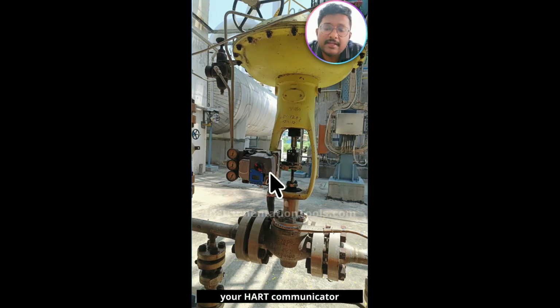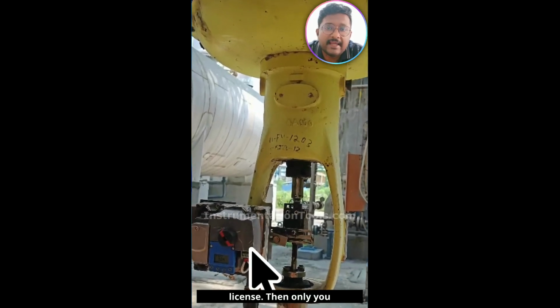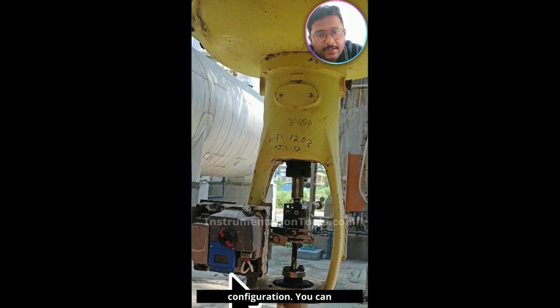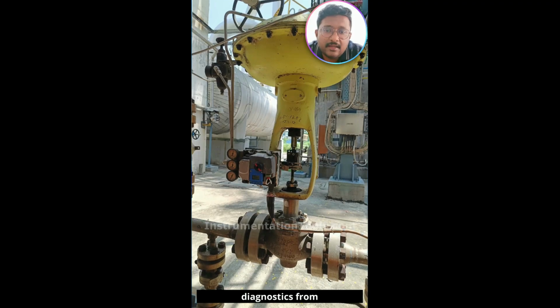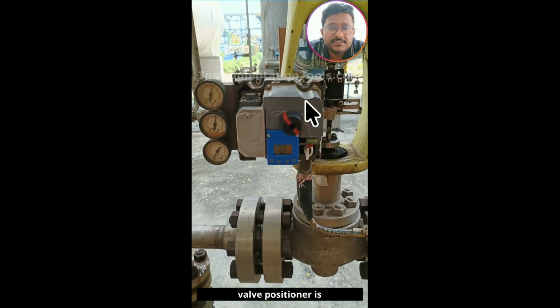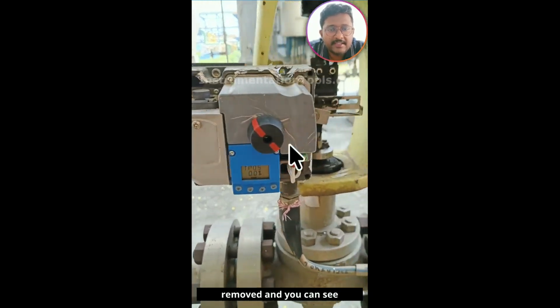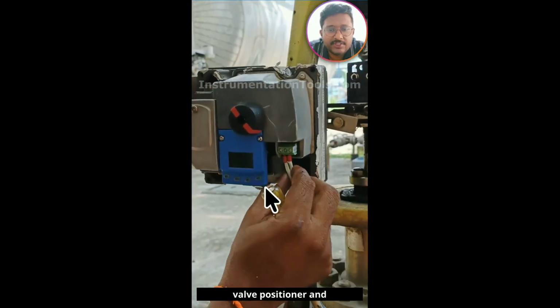Remember, your HART communicator must have a fieldbus license. Then only you can view the data, you can do the configuration, you can do the calibration, or you can access the diagnostics from your HART communicator. This is a foundation fieldbus based device, so you must have a valid license in your HART communicator. The top cover of the valve positioner is removed and you can see the inside components of a valve positioner.